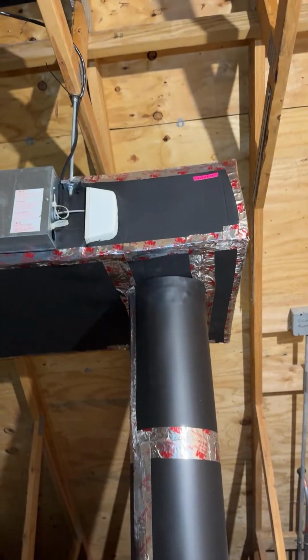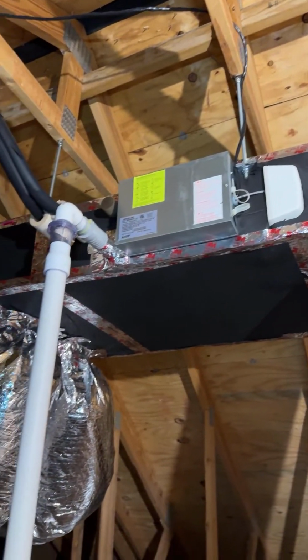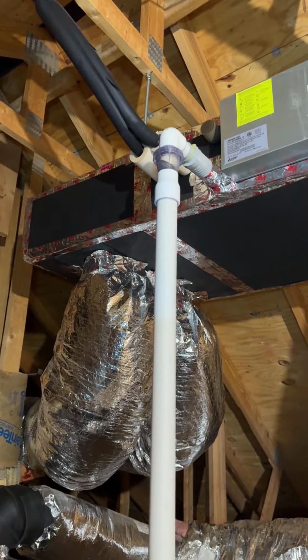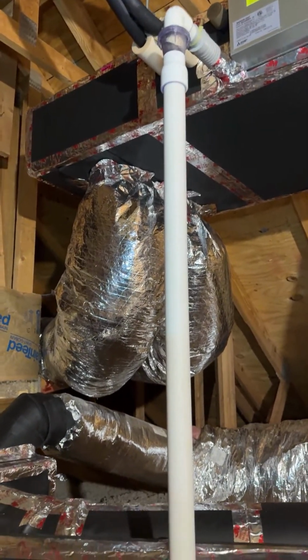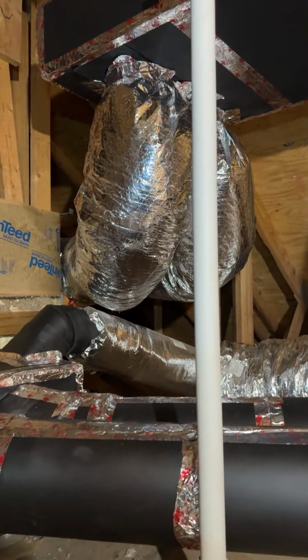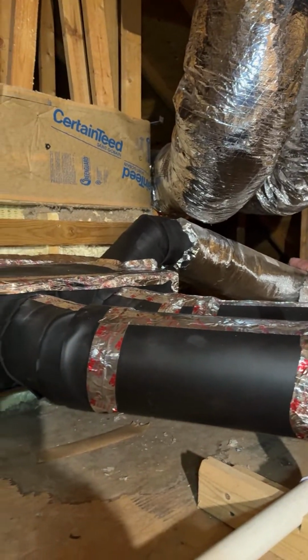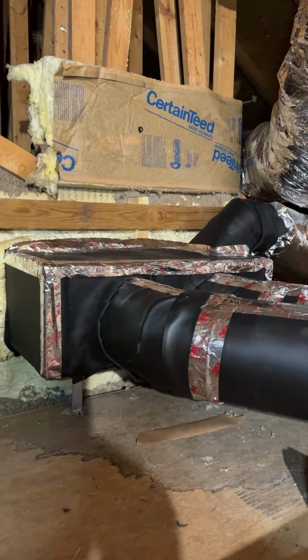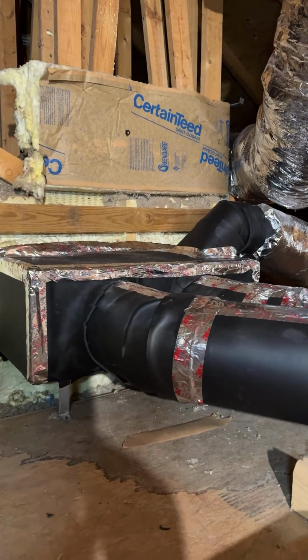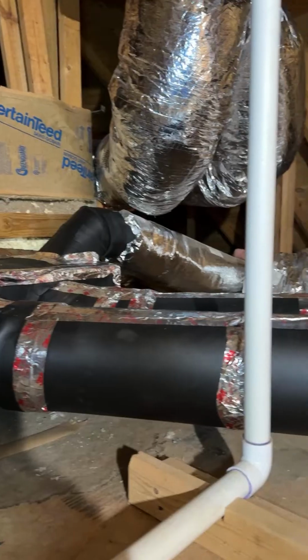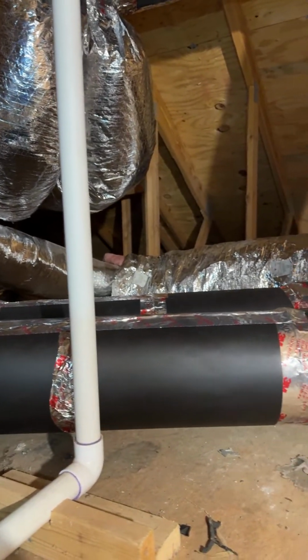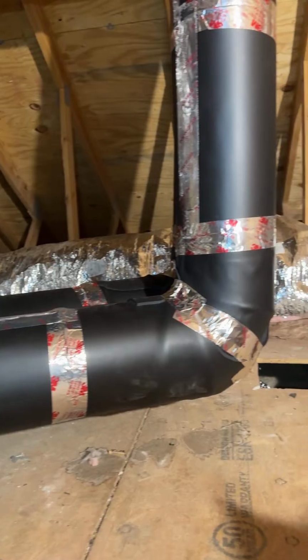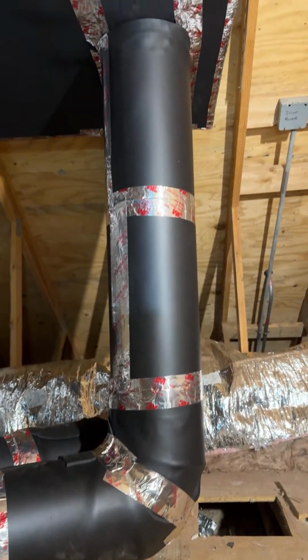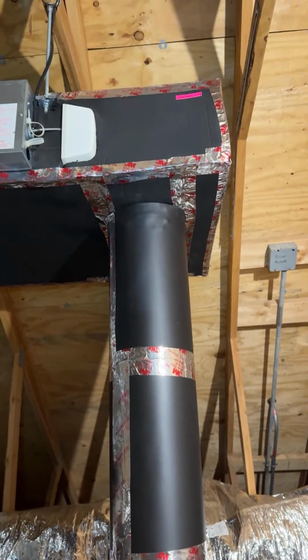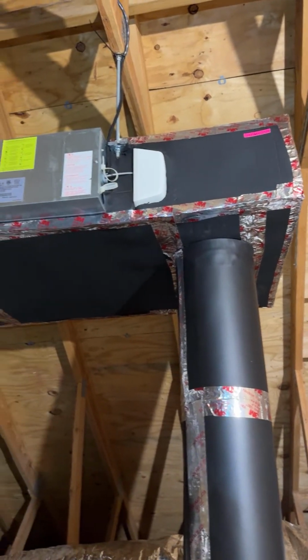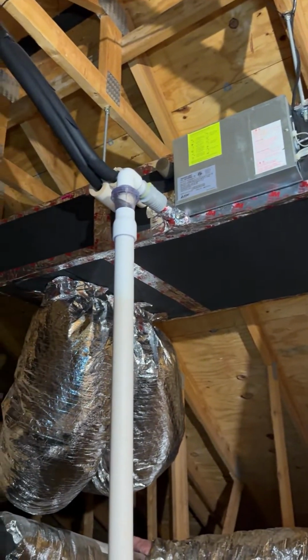Why did we do this? Well, again, this is in an unconditioned space, but unfortunately, this was also a low static pressure system, which means it wasn't supposed to have any ductwork attached to it. So strike two, unfortunately, for our HVAC contractor, who will go unnamed, but this system was not meant to have any ductwork on it. And so what we did is we added these additional returns and the ERV supply to hopefully boost the static pressure to get more of that air into the bedrooms.